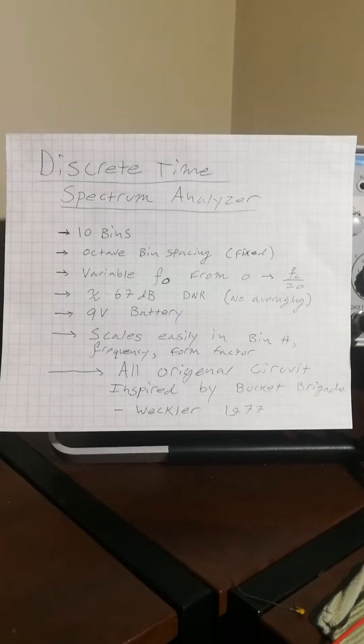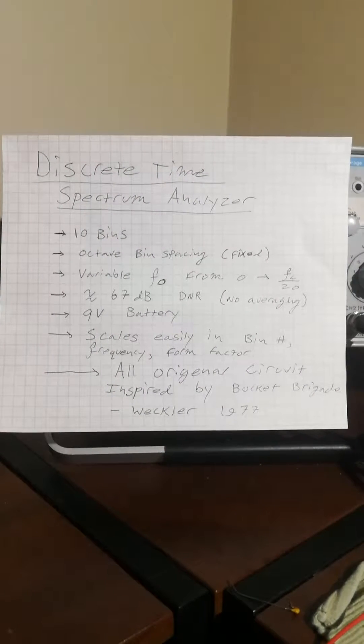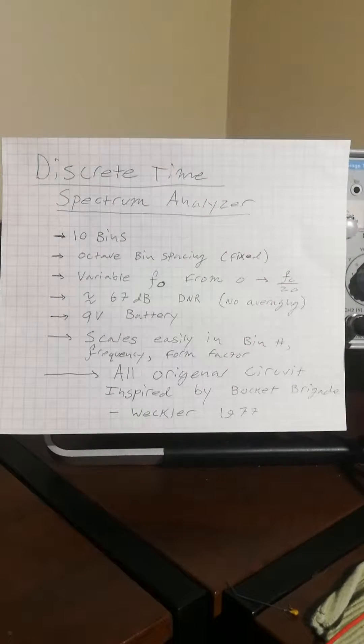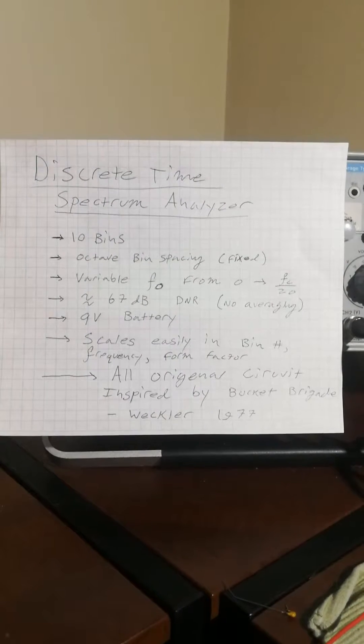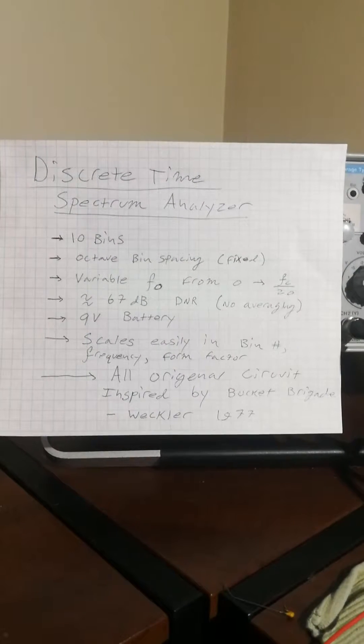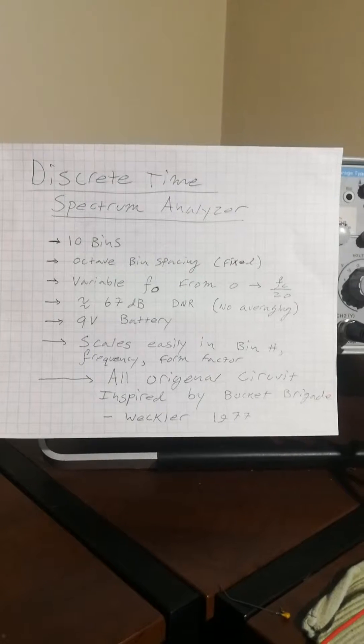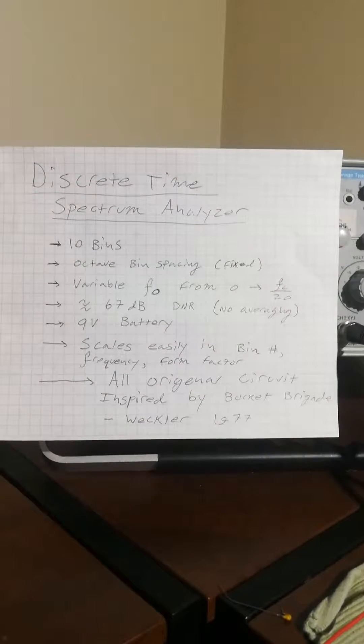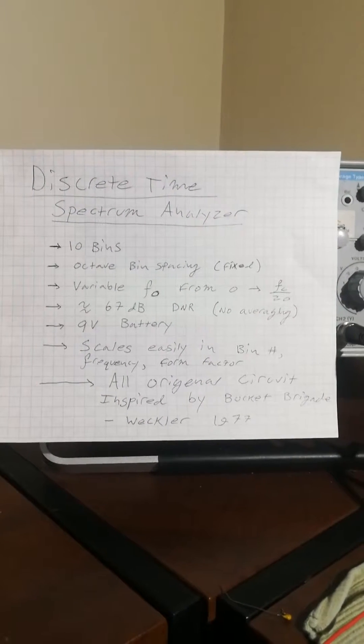In practical spectrum analyzer use, you would implement some averaging which makes the calculation when it's shown on the screen the result of many, many samples of data. Hundreds or thousands in the low end, and at least many tens in the high end.